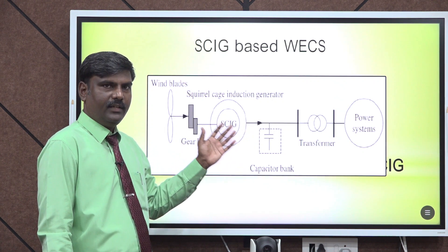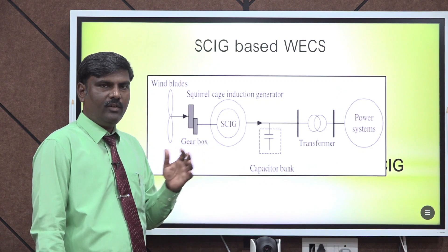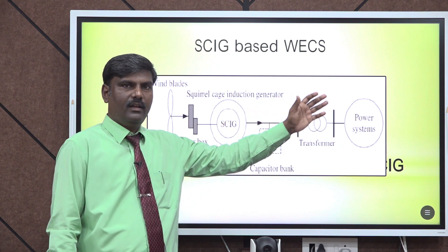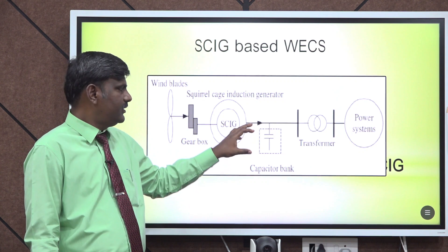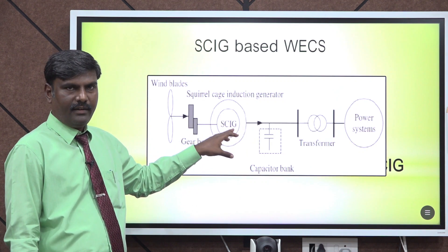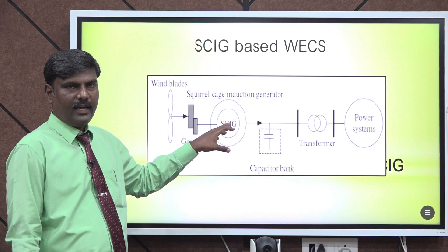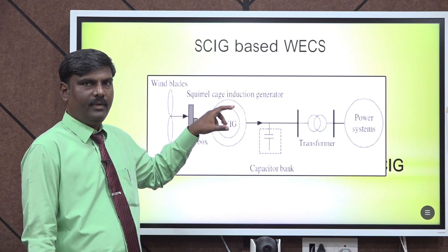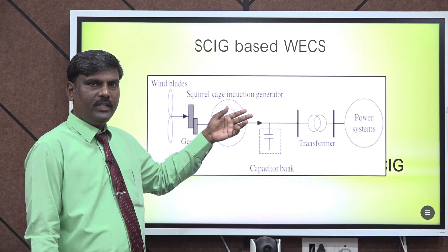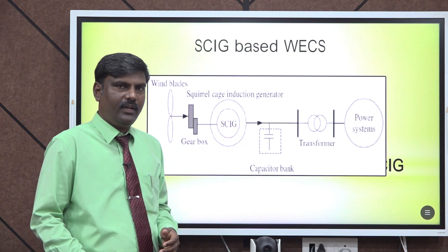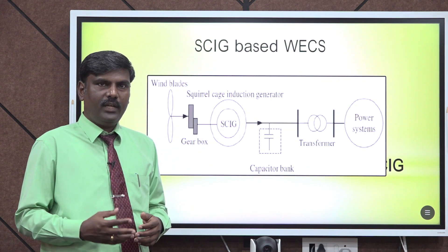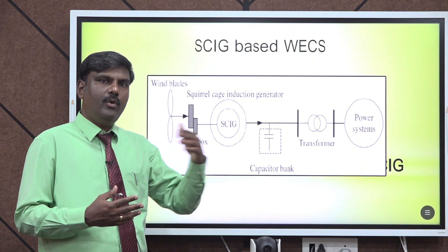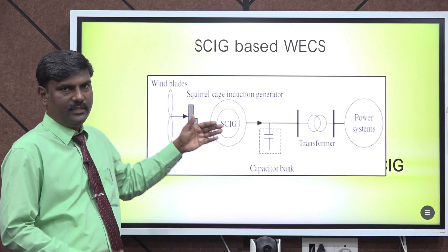During starting of this wind energy conversion system, initially we have to operate this system as a motor. For that it draws power from the grid — this induction generator initially runs as a motor. After that only it is coupled with the wind turbine and the speed of the shaft is brought to more than the synchronous speed, because we have to bring that speed above synchronous speed and for that external input is needed.